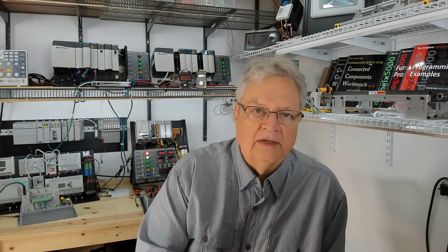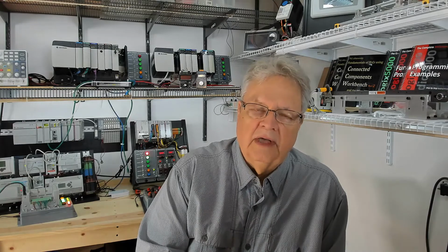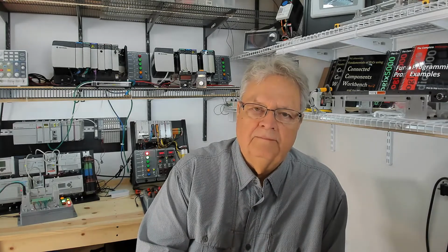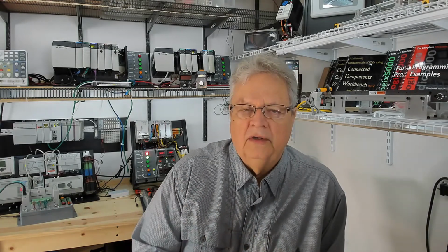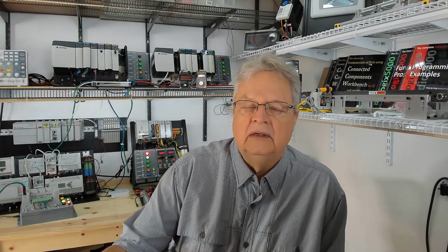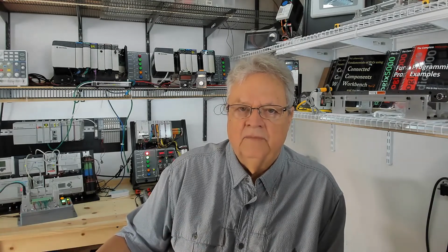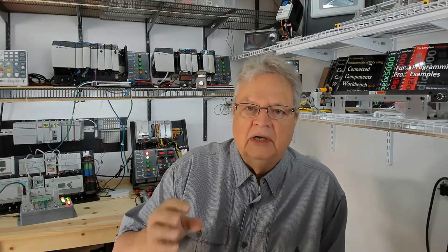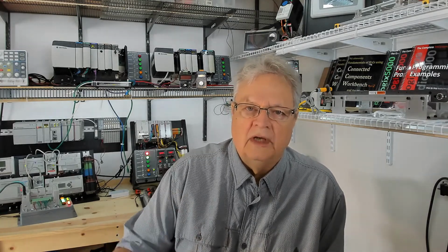Executed the ladder logic diagrams. Then when it came time to update the outputs, it would turn on an output card, put the state of those outputs on the backplane. It would go through the card and then be held for the next cycle on those outputs. Active backplane because it activated the modules one at a time.